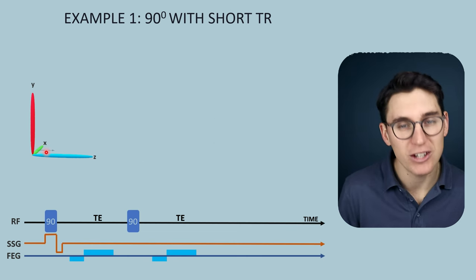The flip angle giving the greatest transverse magnetization for this specific tissue at a specific TR is known as the Ernst angle. For a second tissue with a longer T1 — taking longer to recover longitudinal magnetization but at the same TR — the signal values are different and the Ernst angle would be slightly lower. The flip angle that gives maximum signal is lower because recovery happens more slowly in tissue with longer T1.